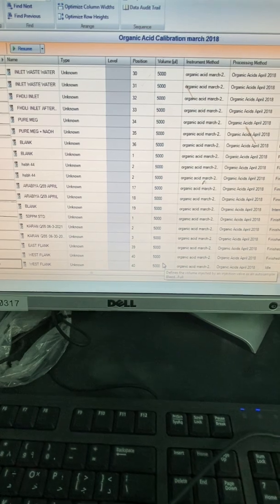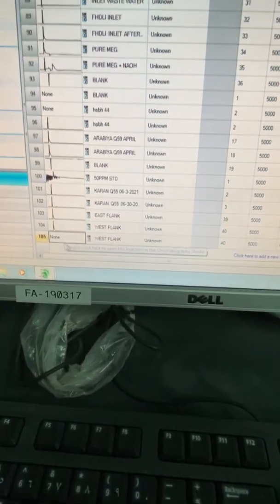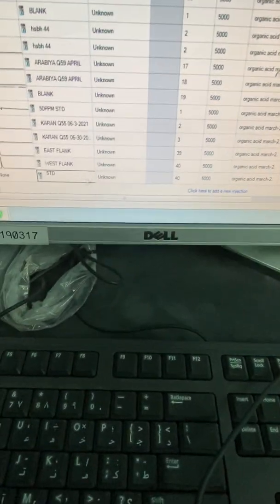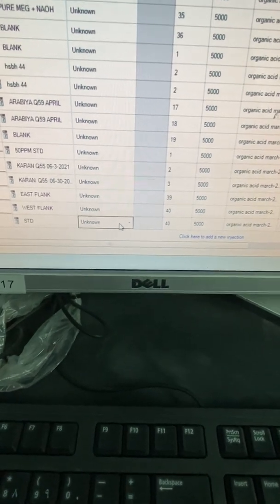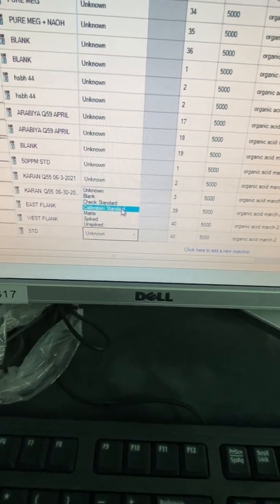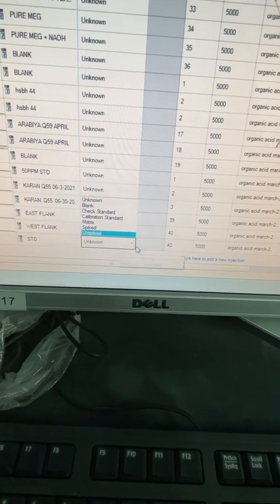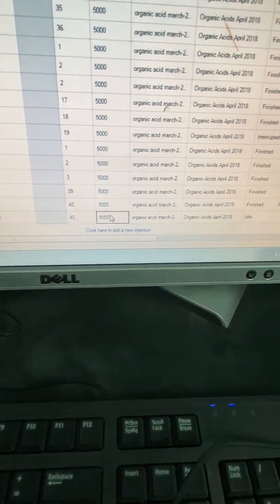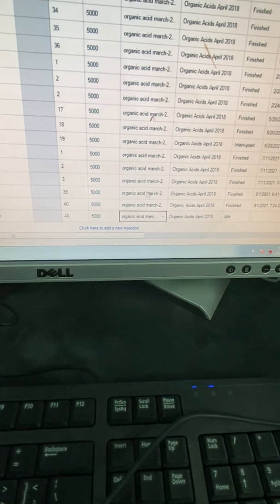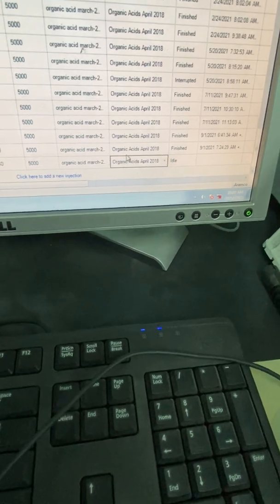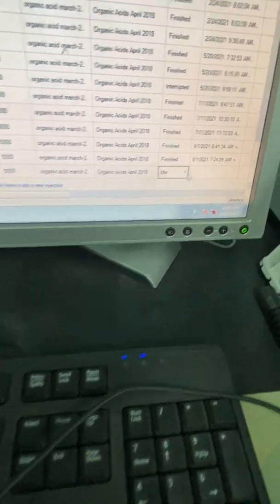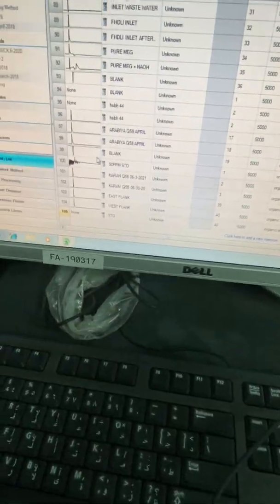Now, once you create your own method, you will start injecting the samples. So you have to press, click new sample. Here still none, because no chromatogram is there. You will mention the sample name. What type of sample you want. You can start doing the calibration immediately by naming the sample like, is it blank? You will start with blank. Or calibration standard. You have to mention what is the level of the standard that you have. The position in case you are using auto sampler. The volume of the sample injected. What type of instrument method. This is the instrument method that we just did now. This processing method, if you don't have process method, you can create it after. The sample will be still idle. It was not yet started. Once you press resume or start, the analysis will start.